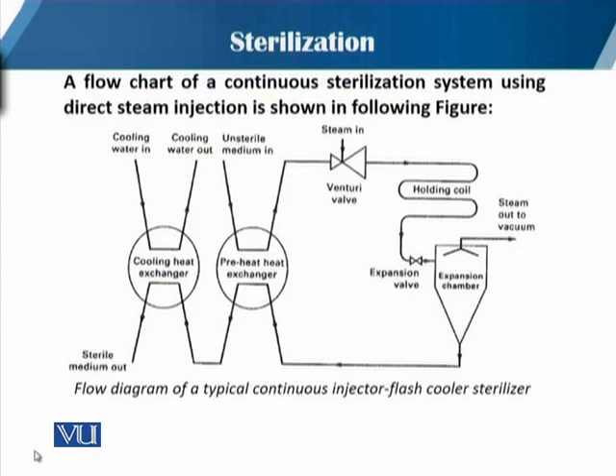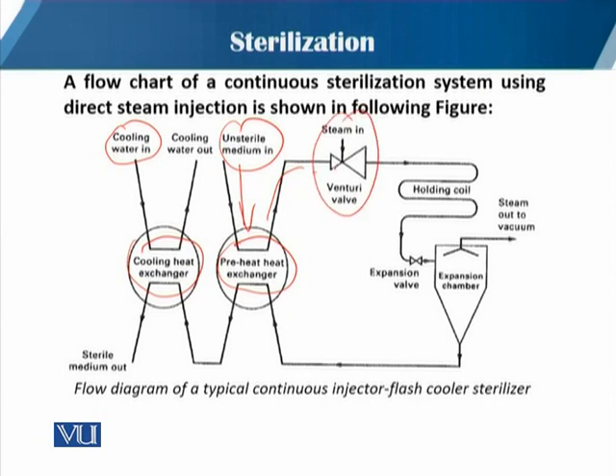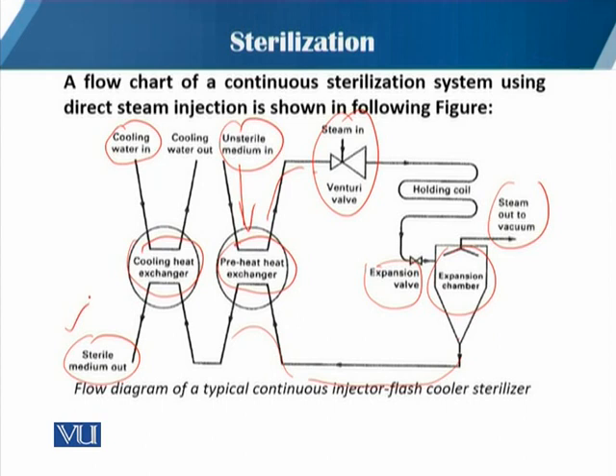In this slide you can see the whole system of continuous sterilization using direct steam injection. You can see the cooling heat exchanger and the preheat exchangers. Cooling water flows in and out, the unsterilized medium is injected, steam is directly introduced, and then there is the holding coil, followed by the expansion valve and expansion chamber. Steam goes to the vacuum, and then the sterilized medium is obtained. This is the typical flow diagram of the continuous injector flash-cooler sterilization system.